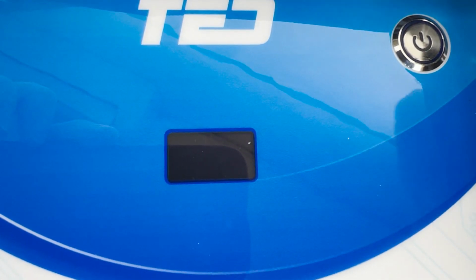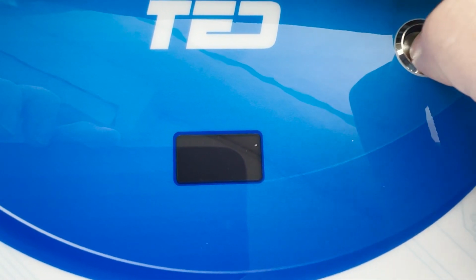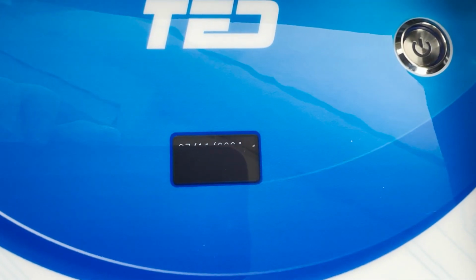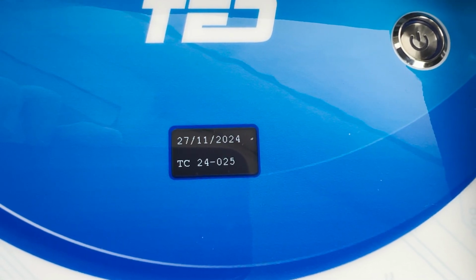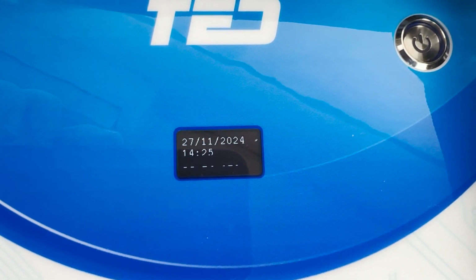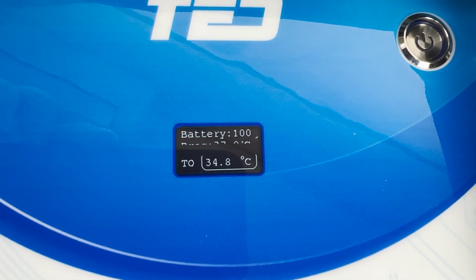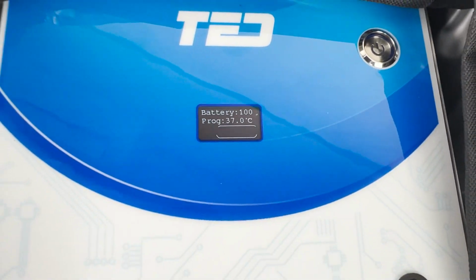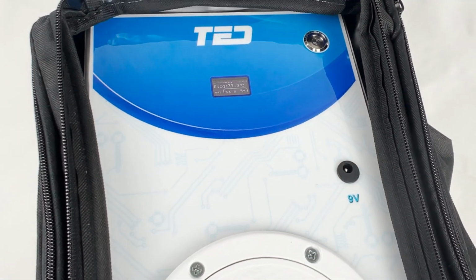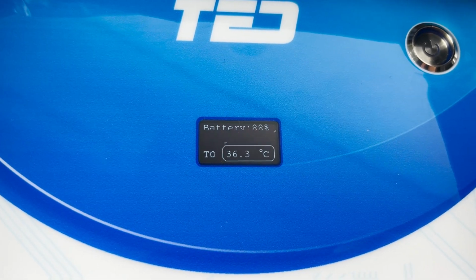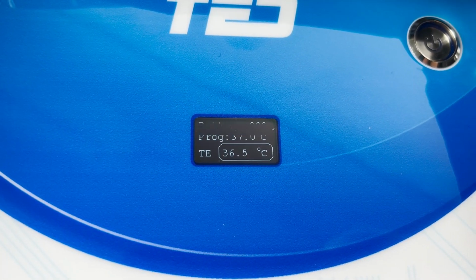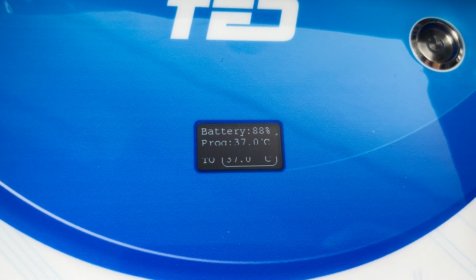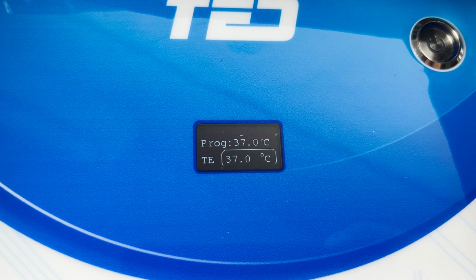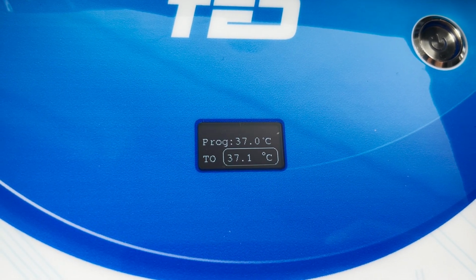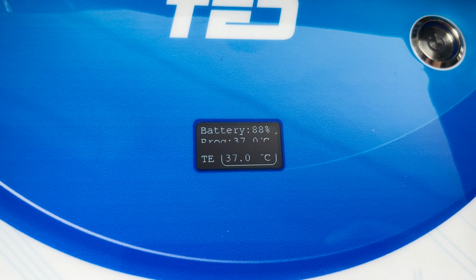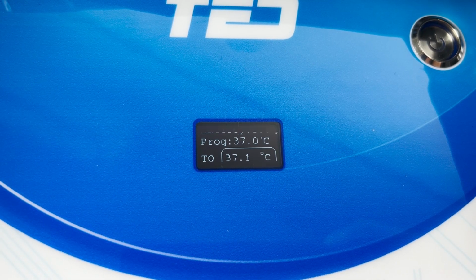After charging the battery, turn on the equipment by pressing the power button on the top panel. The date, time, and serial number of the device will be displayed. At this point, check that the date and time are the current ones for your region and that the serial number matches the serial number on the label on the side of the device. After starting the equipment, it will enter heating mode until it reaches the temperature pre-configured in the set point. After stabilization, it will control and maintain the temperature at the desired value. The display shows information on battery percentage, program temperature, and current temperature.